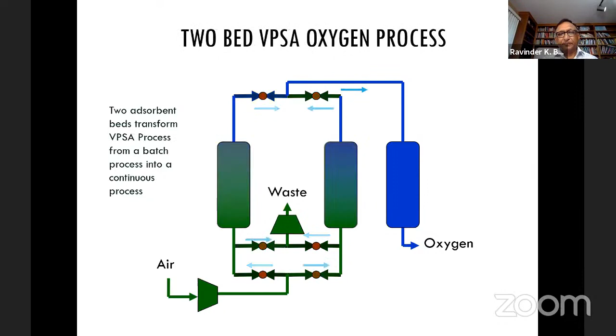So if we look at a pressure vessel which has a sorbent and we pass, can you see my pointer? Can everybody see my pointer? Yes. Okay, so air is passed through the bed and nitrogen is getting adsorbed, and then part of it is fully saturated, and the oxygen level there is 21%, but as it goes through the bed, the oxygen level is increasing because we are trying to produce 95% pure oxygen. At a certain point, it becomes 95%. And that is the only active part of the bed, from the time where it starts separation up to when it becomes 95%.